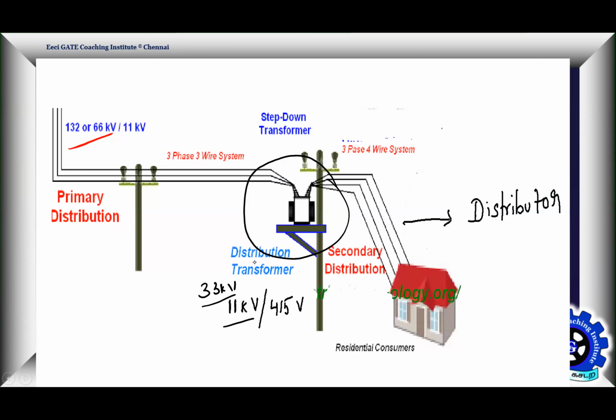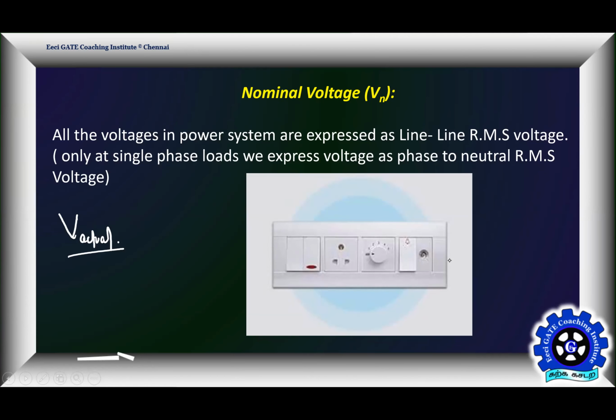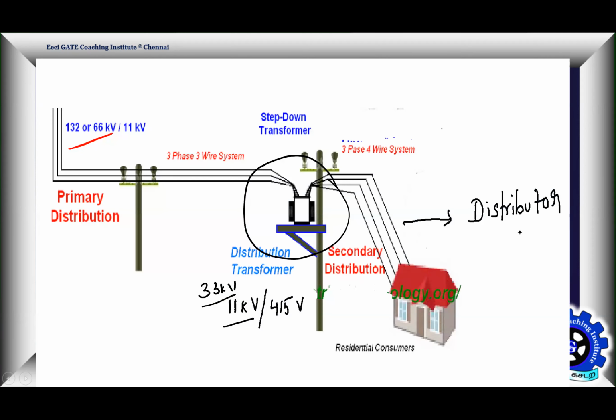Similarly, to get 230 volts in your household 3-pin sockets, what should be the voltage in the distributor running in front of your house? What is the nominal voltage of that distributor? Let's assume this is the distributor running in front of your house - what should be the voltage between the two conductors in this distributor? 400 volts, or sometimes 415 volts. This voltage - 415 volts - is called the nominal voltage of the distributor.